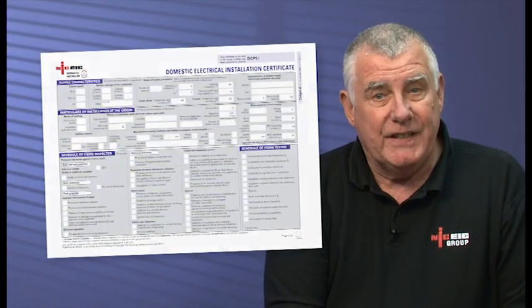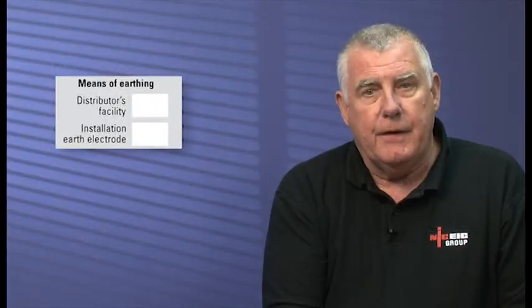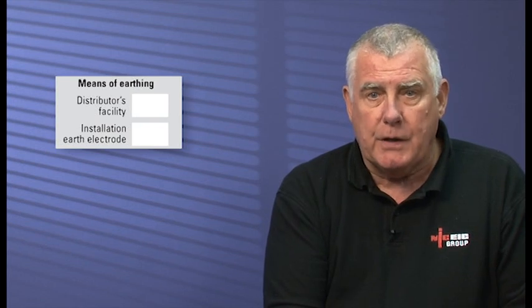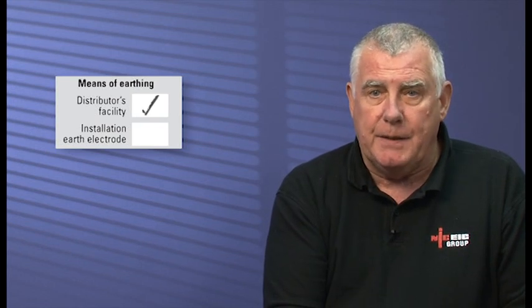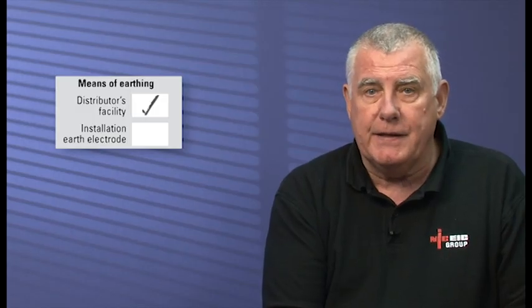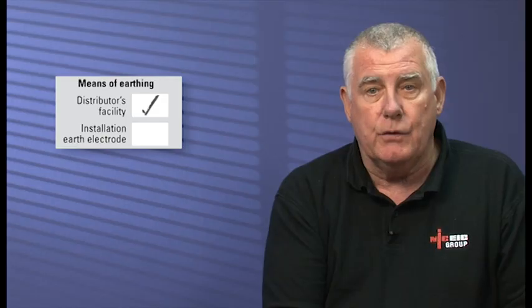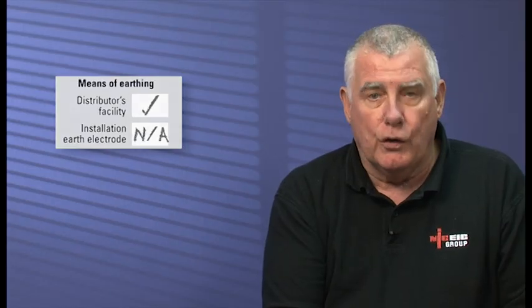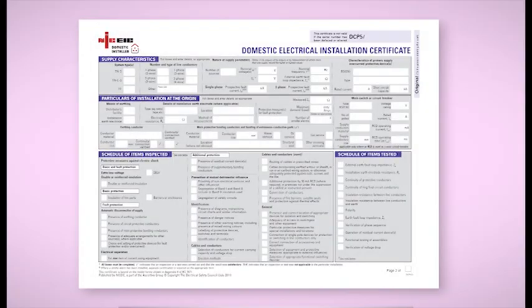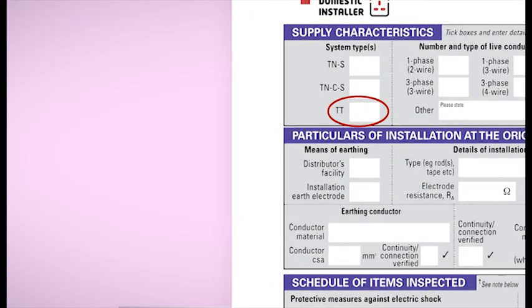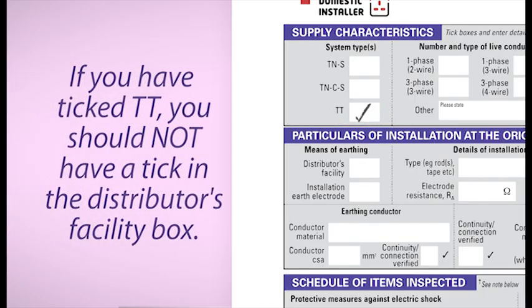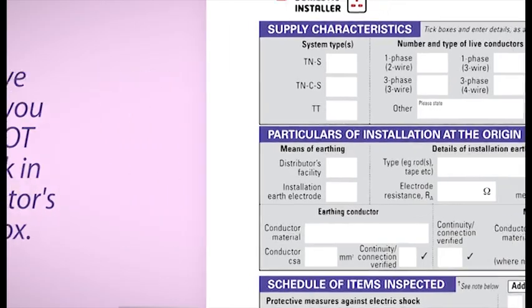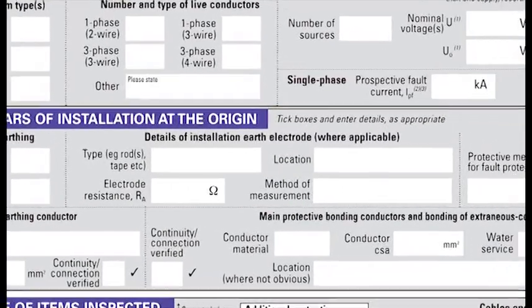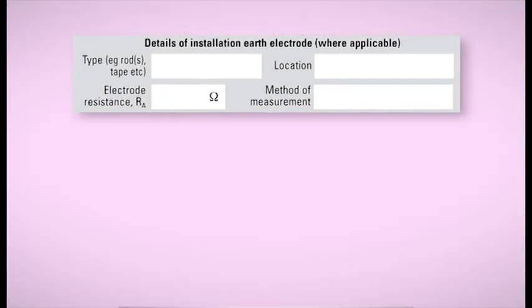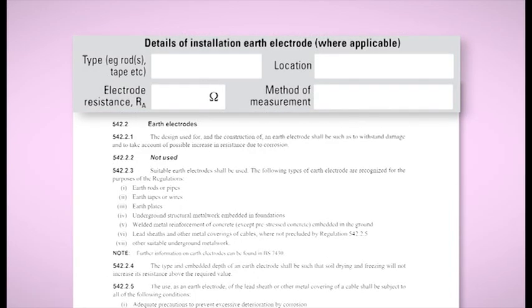The next group of boxes deals with the means of earthing. Now, if you have an earth provided by the electricity distributor and you tick the distributor's facility box, there is no need to fill in the remaining details about the installation earth electrode, other than to write none or not applicable. This should also reference the system type box. So, for example, if you've ticked TT, you should not have a tick in the distributor's facility box. However, you should insert a tick in the installation earth electrode box.